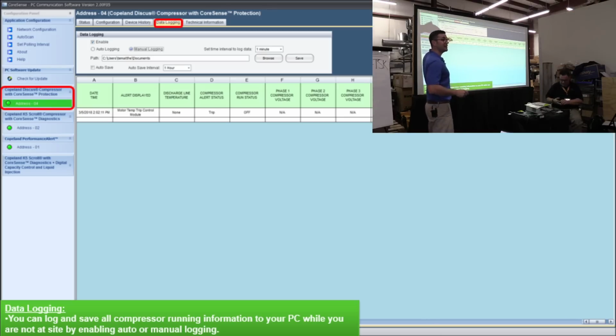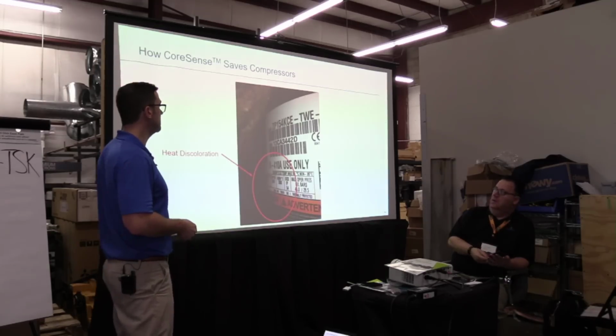So if you want a data log now, just say like Don said, you have an issue with a compressor and you can't figure it out, and you use that performance model. You can start data logging what's going on with that compressor. What's the discharge temp at 2 o'clock in the morning? Right, so now you're trying to monitor the system. Was that the time that the end user left the door wide open, or washing out the coil and freezes the coil up, something like that? It washes out the oil of the compressor because you're getting a little bit of flood back. That's why it tripped on oil. Putting these things together from a device like this.